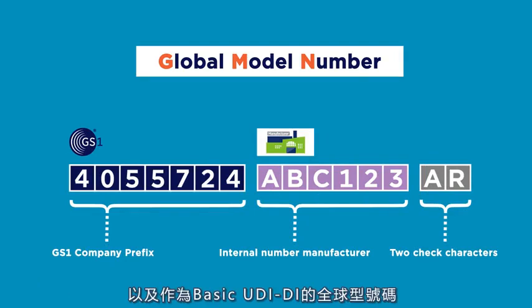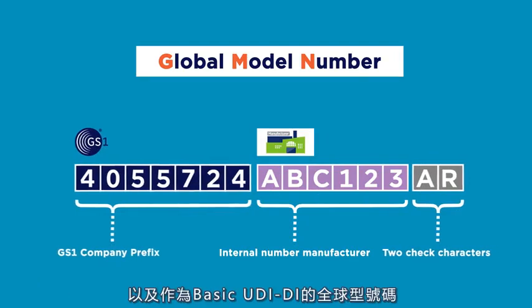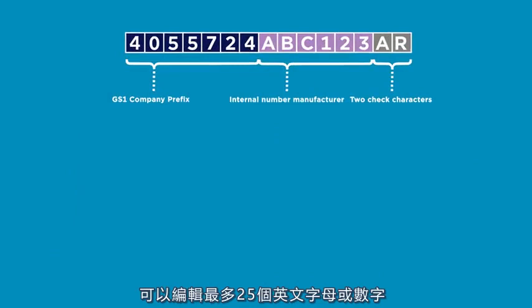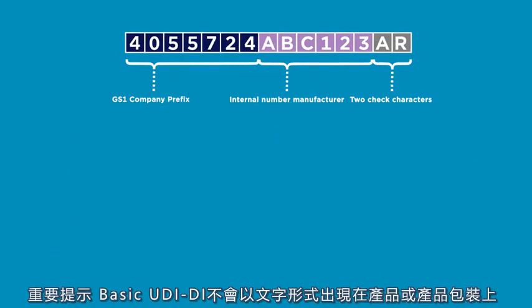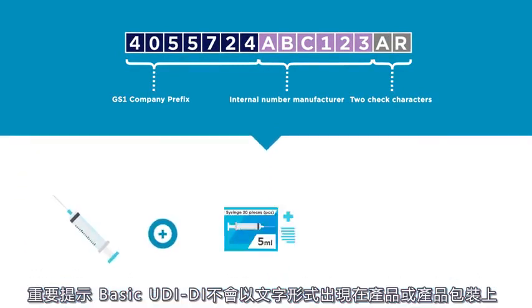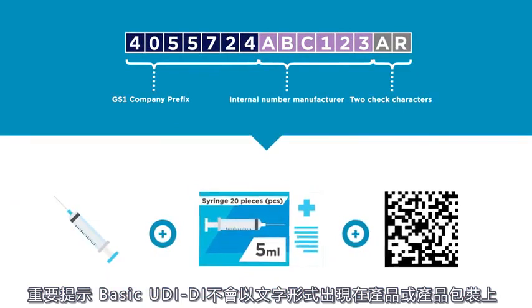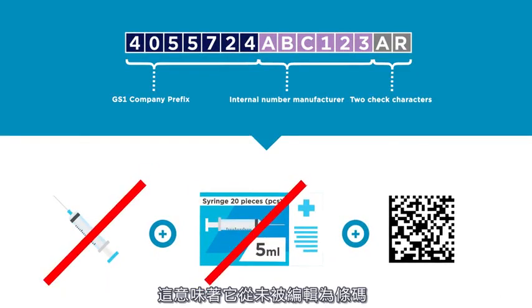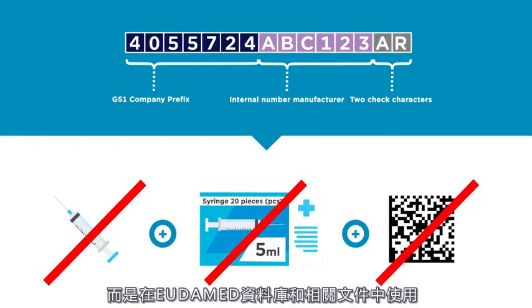The global model number — that is the basic UDI-DI — which can be up to 25 characters long, is ready. The basic UDI-DI does not appear in text form or in a barcode on the products or product packaging. This means it is never encoded in a barcode, but is used in the EUDAMED database and in relevant documents.